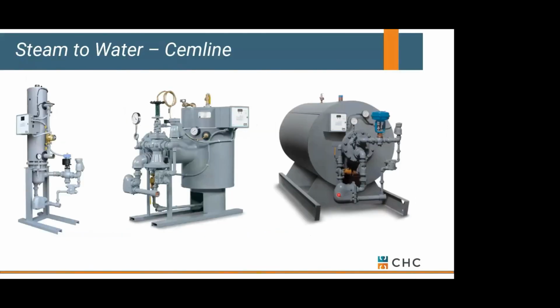I'm just throwing this out there in case you happen to run into a steam application. There's a few manufacturers out there. Cemline is certainly one that is very, very good at taking steam and generating domestic hot water with it. You can do that instantaneously. You can also add a little bit of storage here. Basically, this is simply an inverted shell and tube heat exchanger with a stainless shell. The steam runs through the tubes. The domestic water is on the outside of that. So you come in with cold water and you leave with hot water.